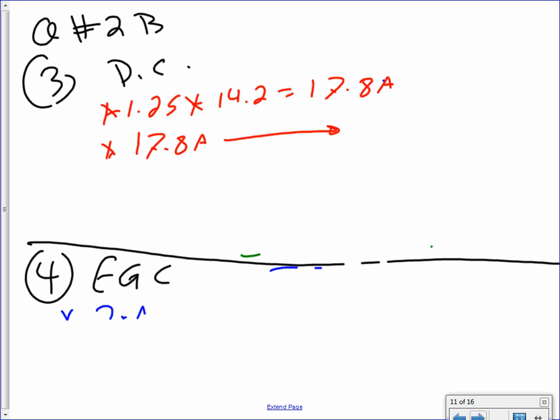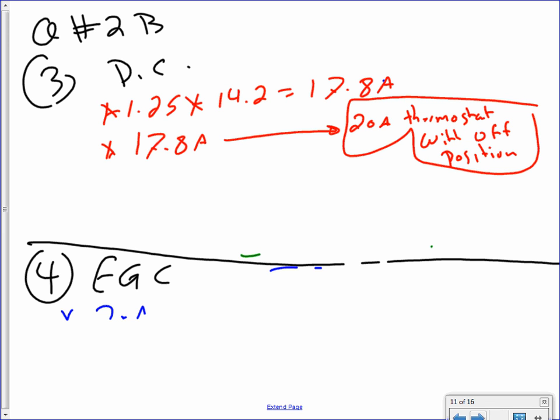Let's go to the disconnect. For the disconnect, I would use the 1.25, multiply it by the same 14.2, which gives 17.8 amps. When you come to here, 17.8 amps, you have a bunch of options. You will have a 20 amp thermostat with an off position. That's my choice, typically.